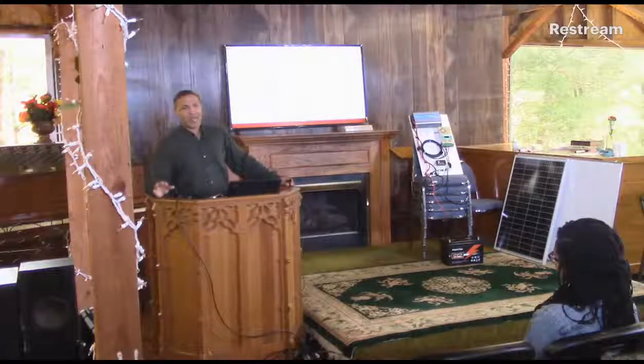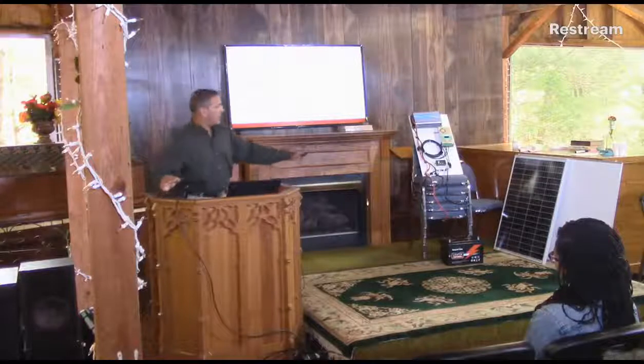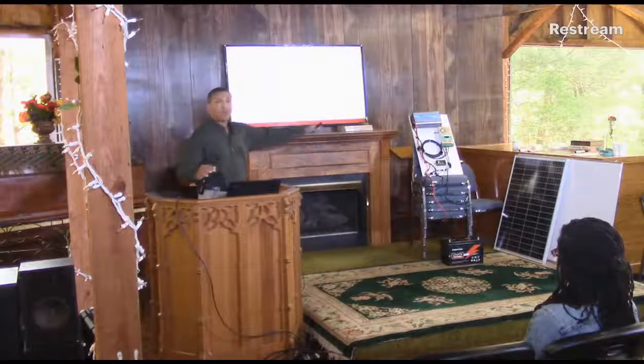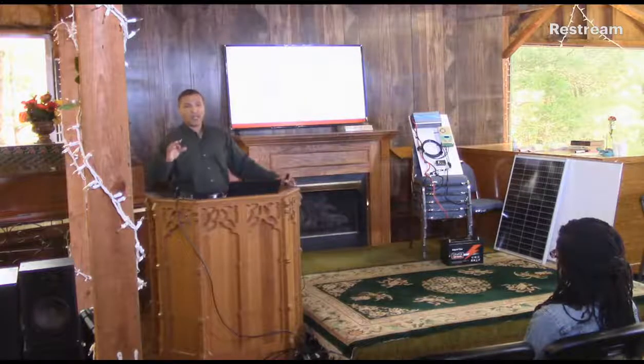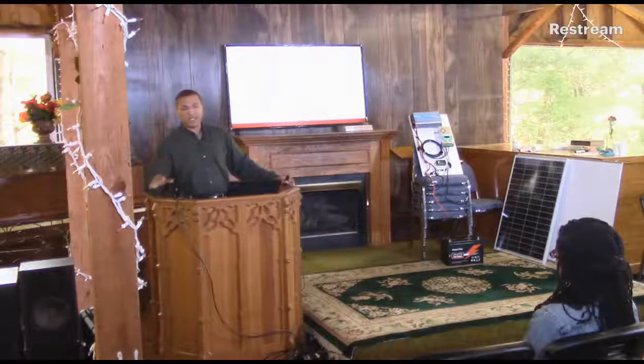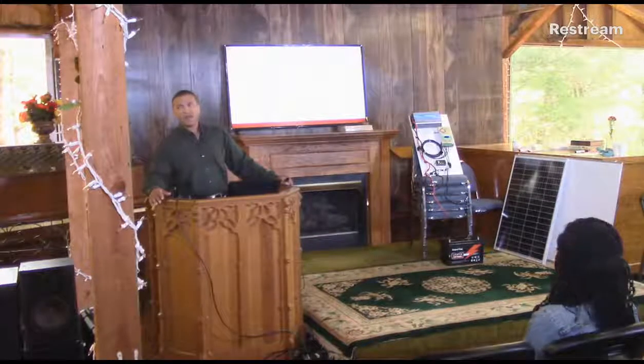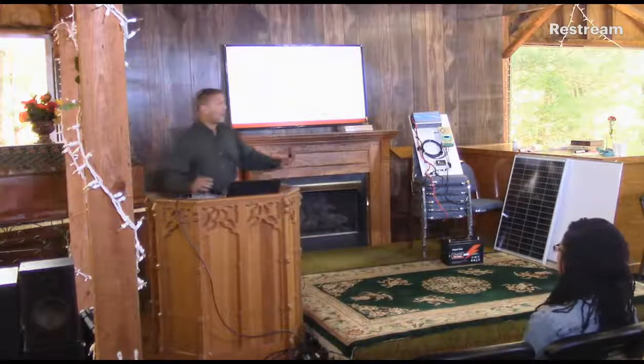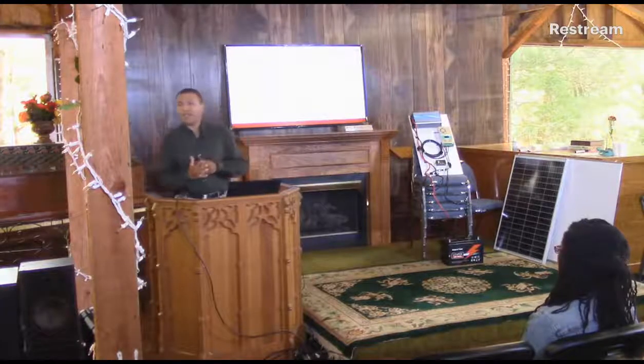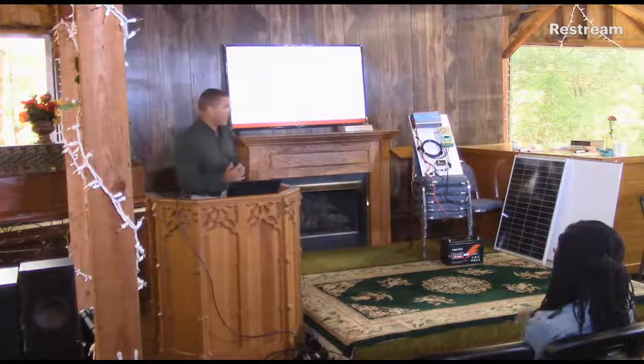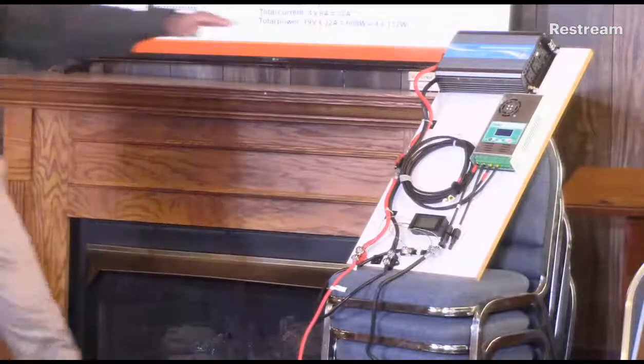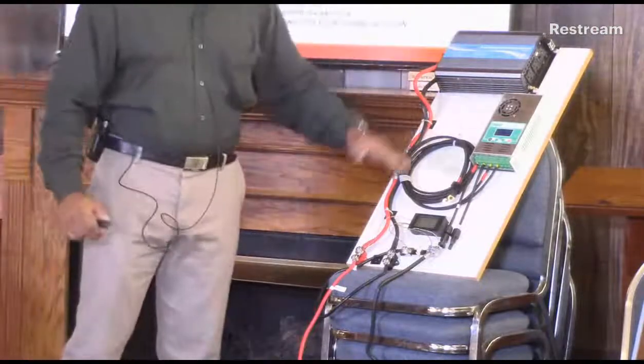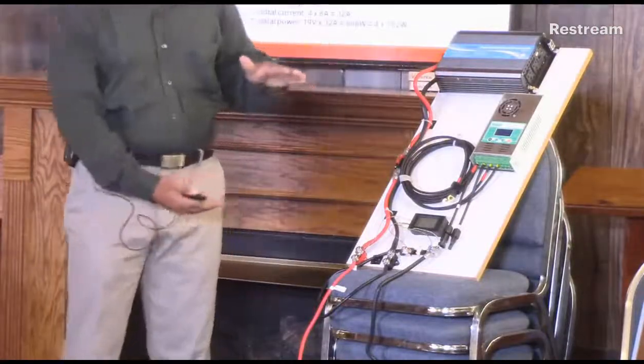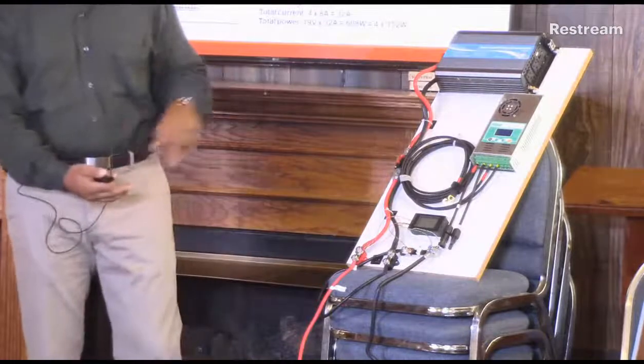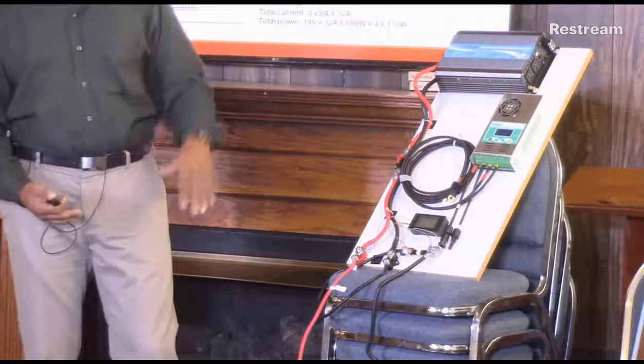So the thicker the wire, especially between your battery and your inverter, the better, because you want that current to flow with no impedance. The thicker the wire from the batteries to the inverter, the better. And you want it to be close. You don't want your inverter down the road and your batteries here.